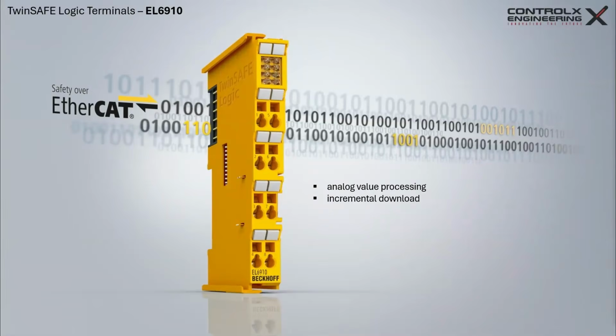Another highlight of the new controller generation with the EL6910 is the incremental download. In contrast to its predecessor, the safety project now consists of 4 components: logic, parameters, mapping, and info data, each of which has its own checksum. This means that when you make a change to your TwinSAFE project, you don't have to download the entire safety project again. Instead, the EL6910 allows you to download only the part that changed.